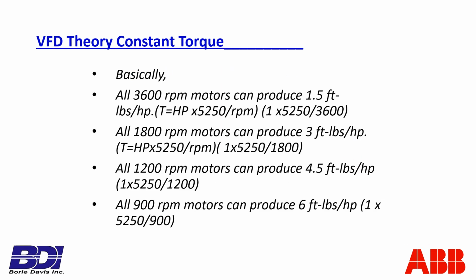Here we are simply showing the different base speed motors: 3600 RPM, 1800 RPM, 1200 RPM, 900 RPM. And if you take that same torque equation, torque is horsepower times 5250 divided by RPM, and if we're just looking at a 1 horsepower motor, then the torque is equal to 5250 divided by 3600 if it's a 3600 RPM motor. You do that math, that comes out to 1.5 foot-pounds per horsepower.